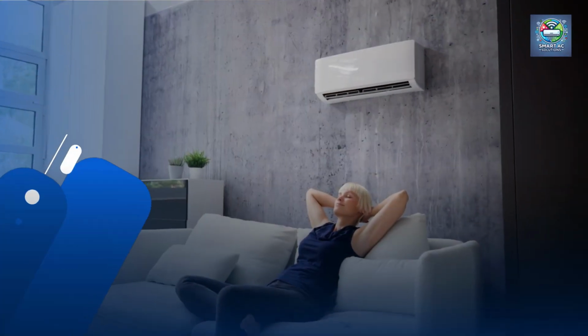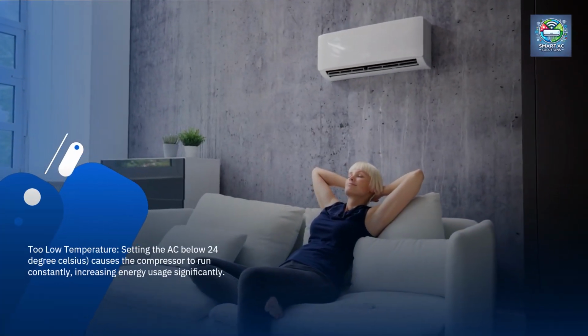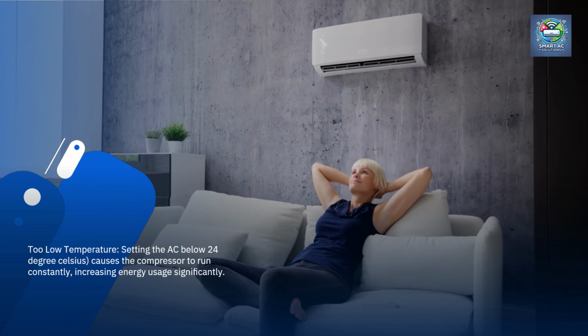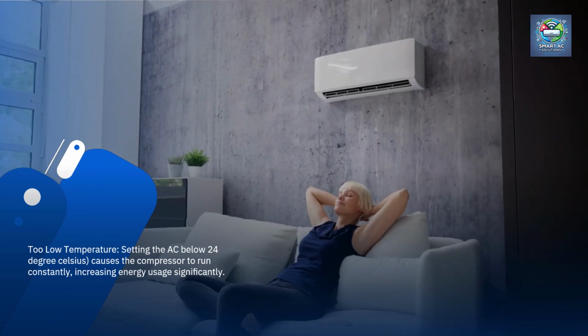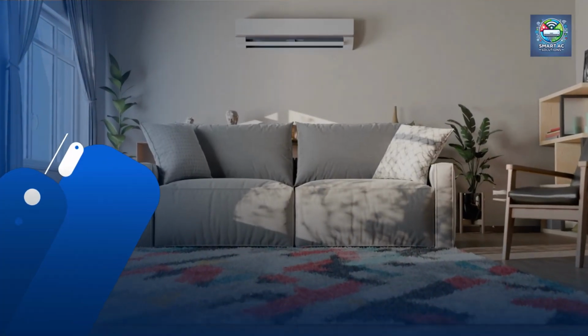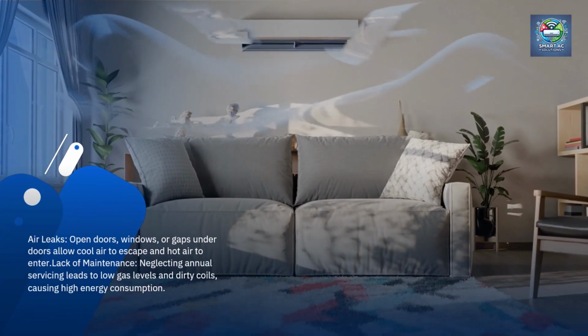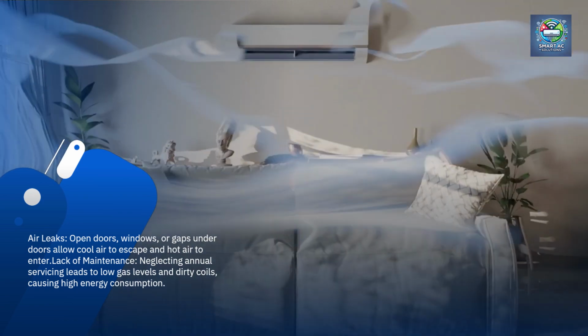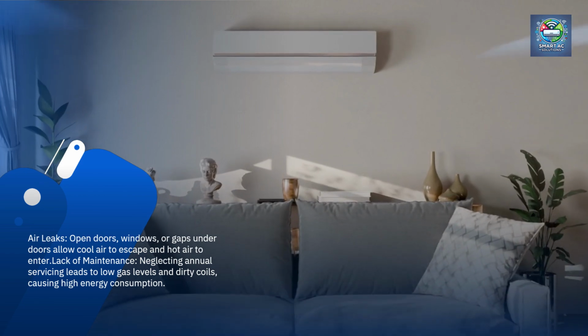power. Too low temperature. Setting the AC below 24 degrees Celsius causes the compressor to run constantly, increasing energy usage significantly. Air leaks. Open doors, windows, or gaps under doors allow cool air to escape and hot air to enter. Lack of maintenance. Neglecting annual servicing leads to low gas levels and dirty coils, causing high energy consumption.